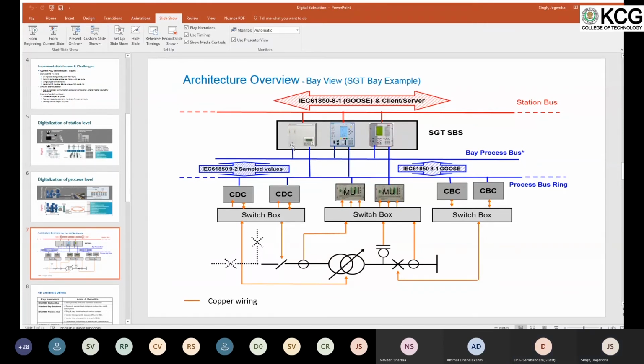So that means both digital substations and the existing conventional substations can coexist. Even at the bay level, they can coexist. In one substation, you can have one bay fully digital and one bay totally traditional. And then how will you get into the IEC 61850? You see, IEC 61850 is from the protection relay to the substation controller.